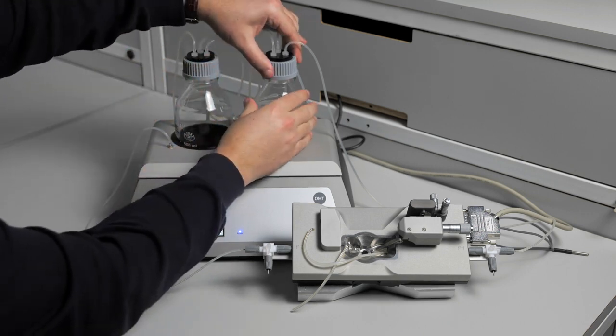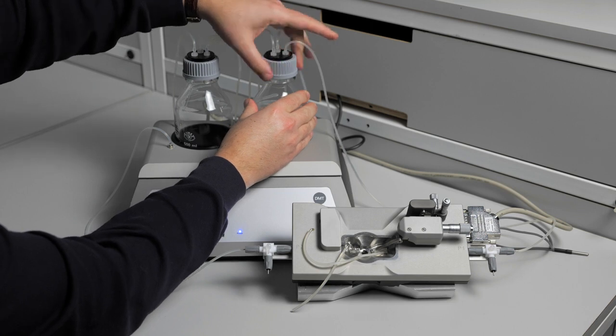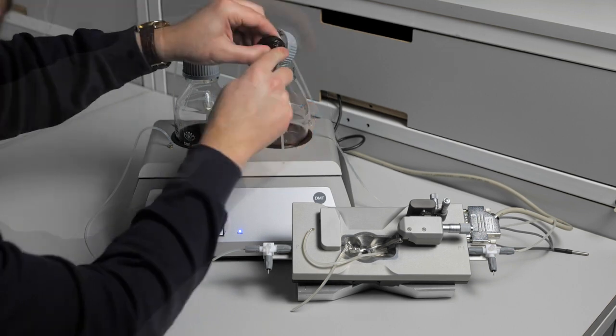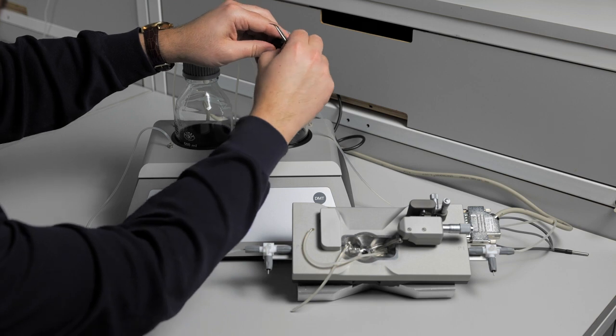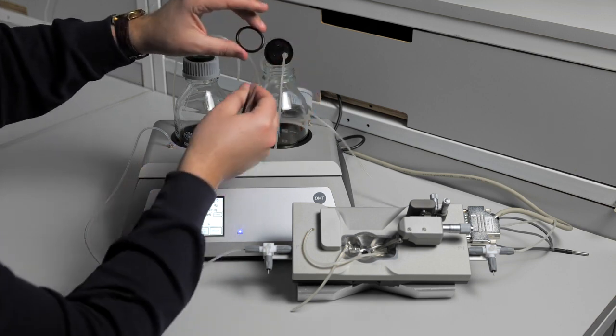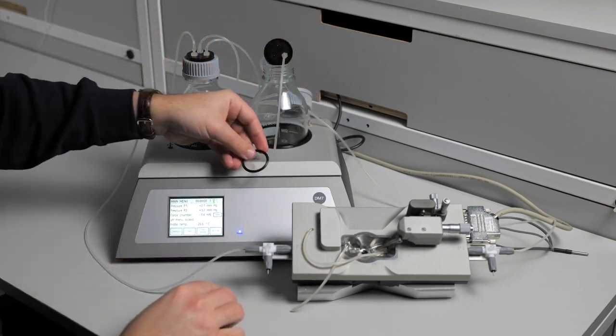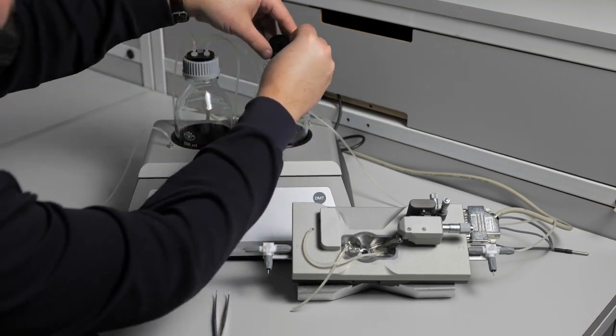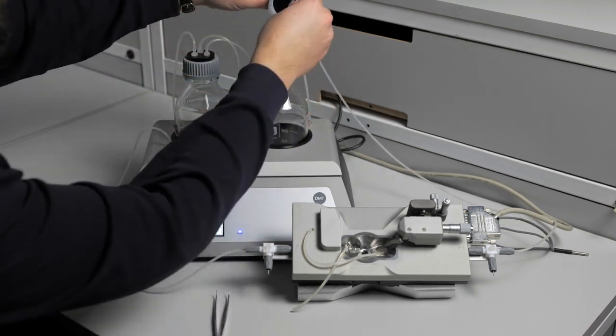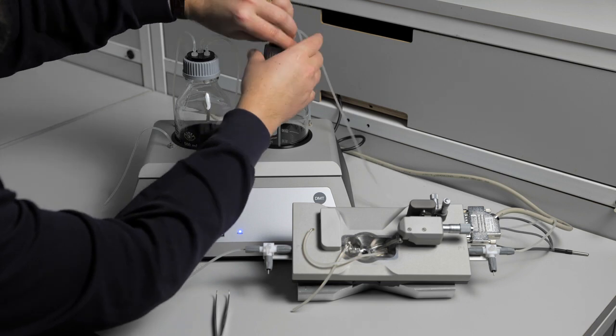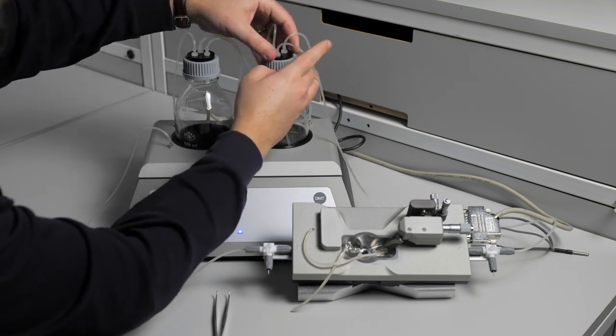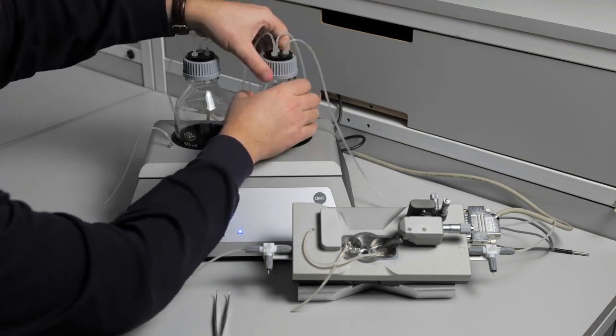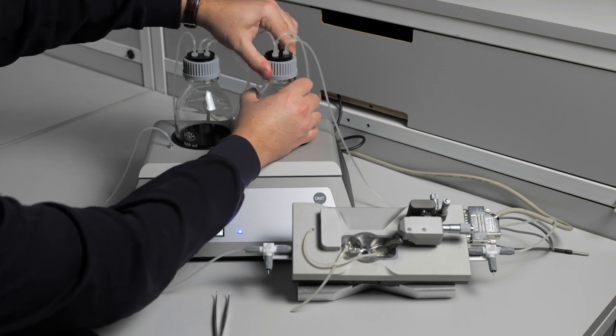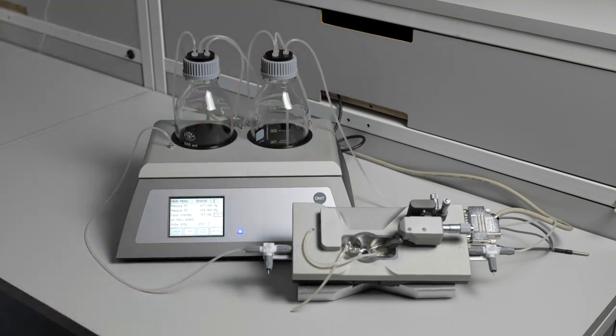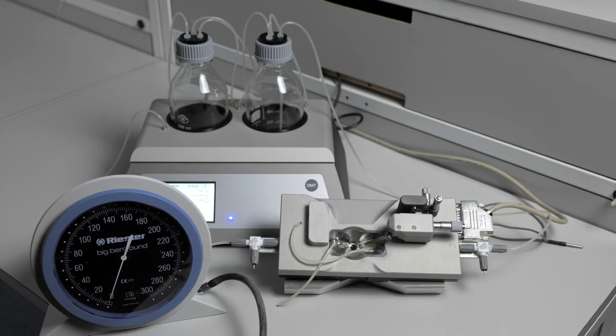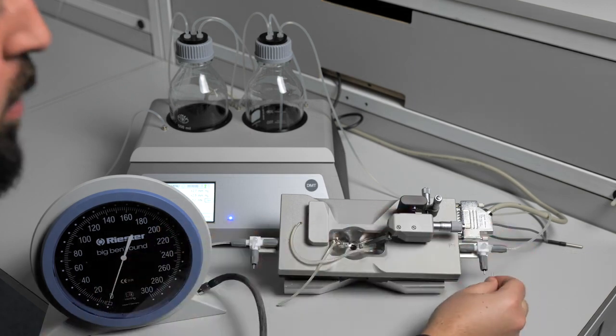Do the same process for the P1 cap. This O-ring is also good. It can go back in the cap and replace the cap on the bottle. You will always want to make sure that your caps are securely tightened on the bottles. After you check the O-rings, check the chamber next.